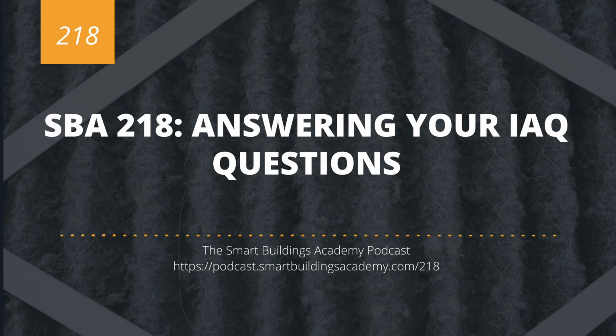Next question, from Todd: what is my opinion of the OA control sequences found in ASHRAE's Guideline 36? That's a really good question. There's an OA strategy, and there's a space pressurization trim and response strategy, and I feel both need to be considered when we're talking about IAQ and viral load in a building. This also relates to Title 24 in California, which has somewhat similar control strategies. But Guideline 36 was all about optimizing the utilization of equipment for energy consumption and demand-based usage.